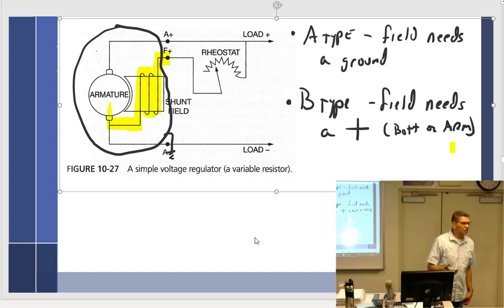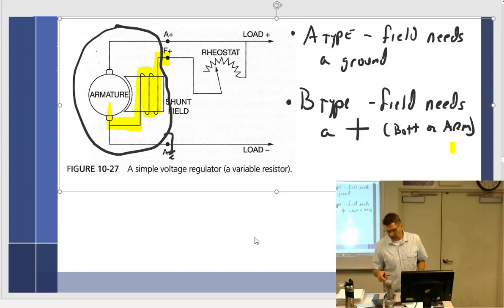Well, one of the tests that you do uses the growler with the 110 probes on the end. By the way, don't grab them and hold them real tight. Did you do that? For like a minute. You learn really quick. It's not a Simpson meter. They're 110 probes. You grab them and hang on to them, you will feel what 110 feels like. It's a little bit of a danger. It will latch you on. It's not too bad. It's not comfortable, but I've done it too. Scare him the first time. This is the one that was shocking himself for fun.